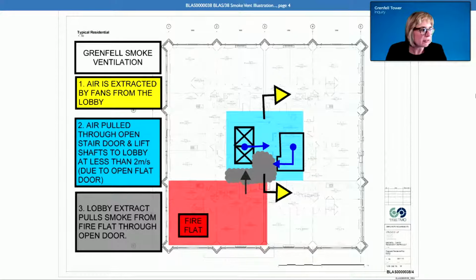Smoke will flow out. The best example is to say we didn't have the extract system at all - purely a lobby without any ventilation. What will happen is smoke will flow naturally into the corridor, through the open door, because the picture you're painting is the door is open so the person can escape from the flat. So when they open the flat door, smoke will flow into the corridor by its own natural momentum, until it finds something else that interferes with it and allows it to go somewhere else, which is likely to be the stairway.